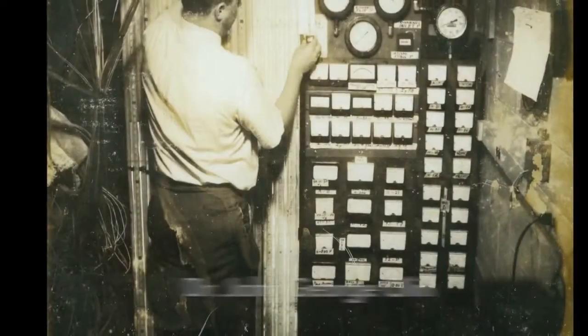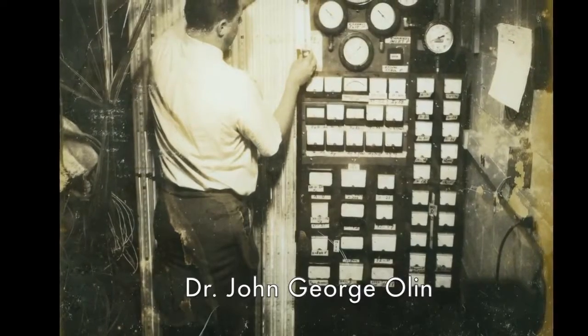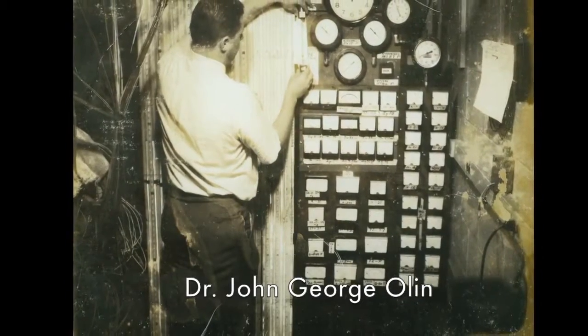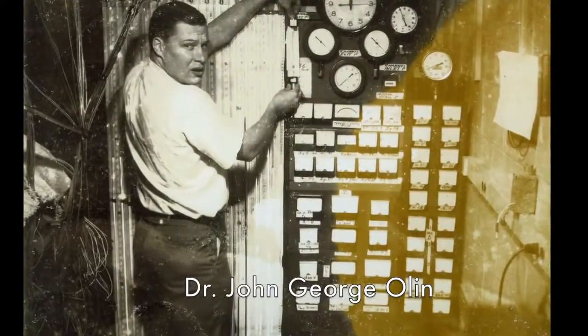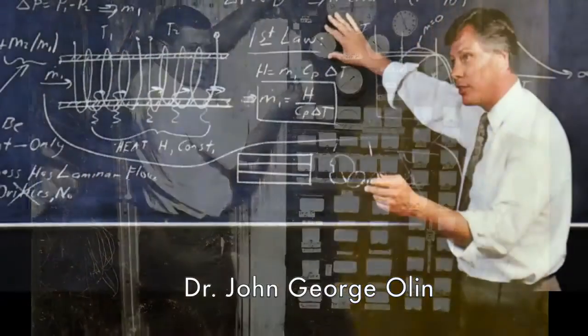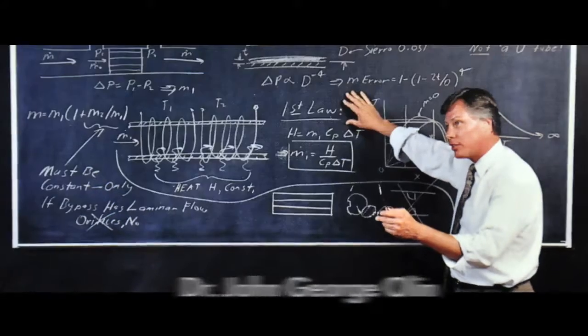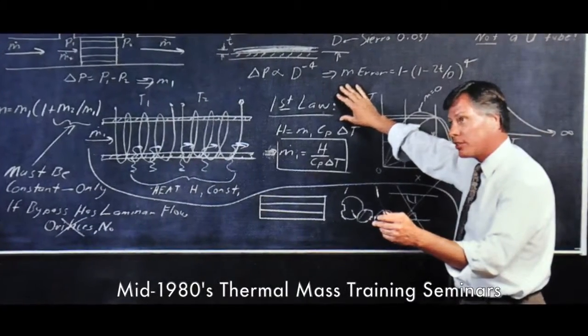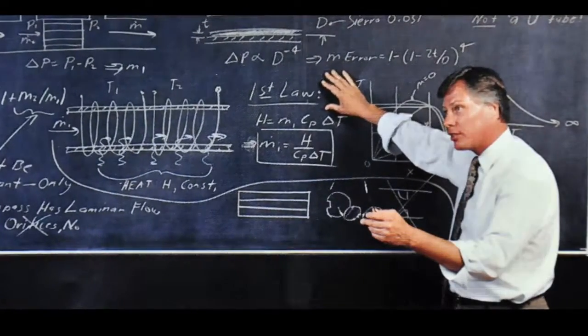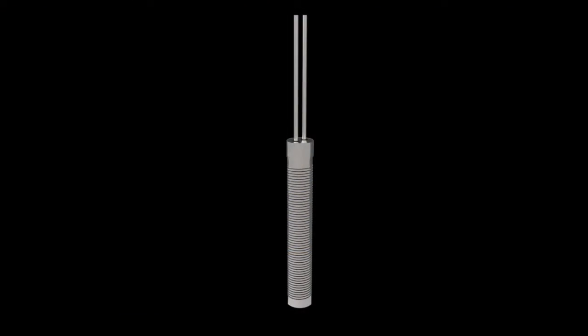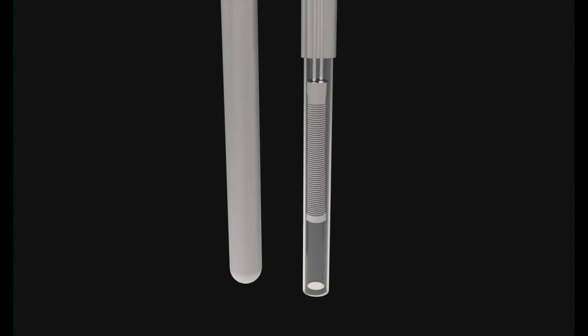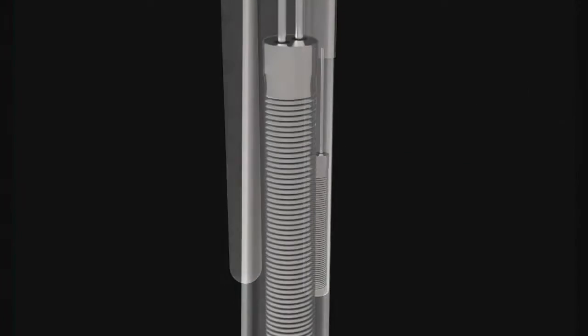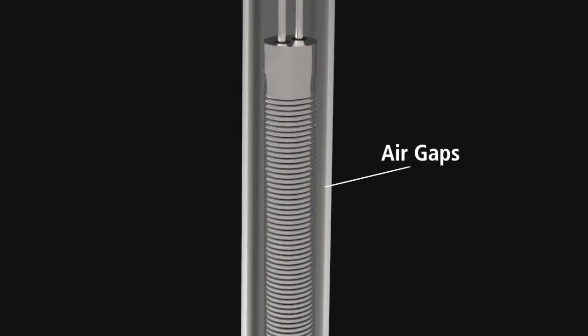It wasn't until much later, when innovators like Dr. John George Olin, founder of Sierra Instruments, saw the rapidly growing need in industry for a truly industrial thermal hot wire anemometer. To make a thermal flow sensor truly industrial strength, Dr. Olin pioneered the innovation of an all-metal clad thermal sensor in the early 1980s, winding platinum wire around a ceramic mandrel and placing it inside a metal sheath called a thermowell. The problem was that the air gaps between the thermowell and the platinum wound mandrel needed to be filled to assure stable heat transfer. This was the key to assuring an accurate and stable thermal mass flow meter.